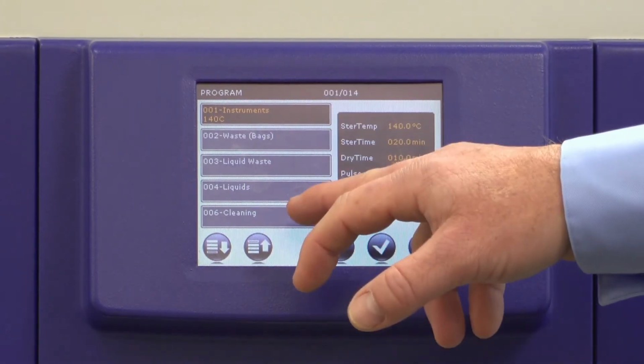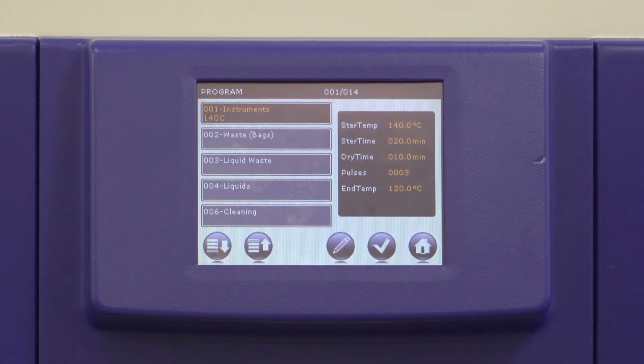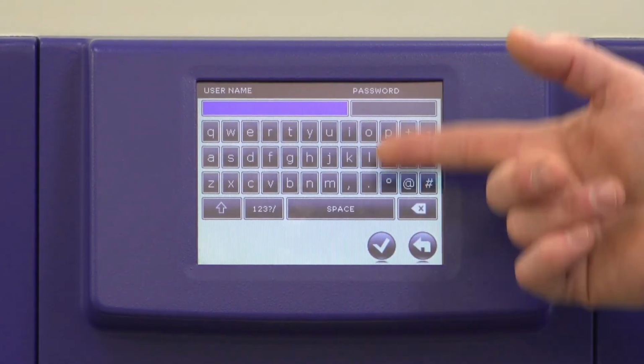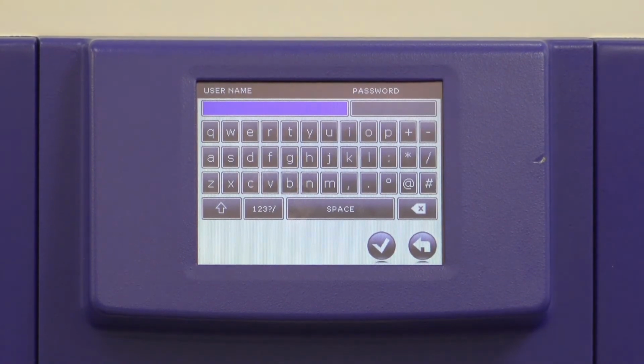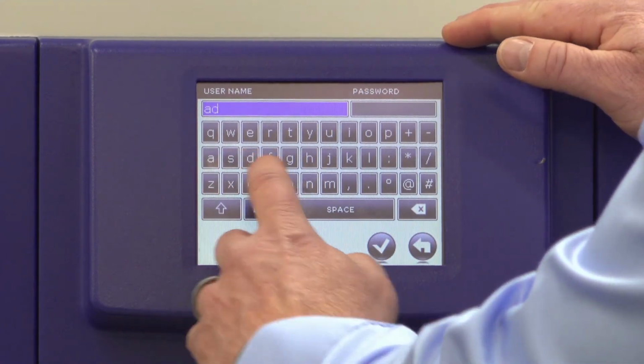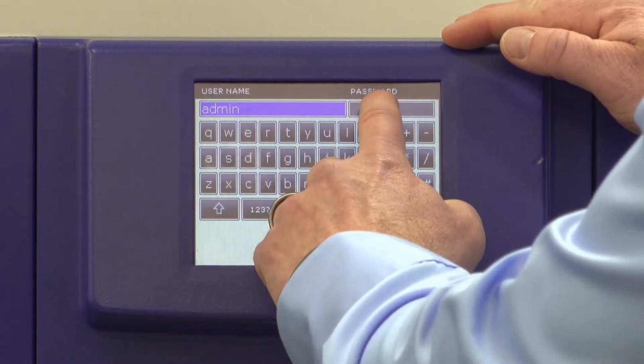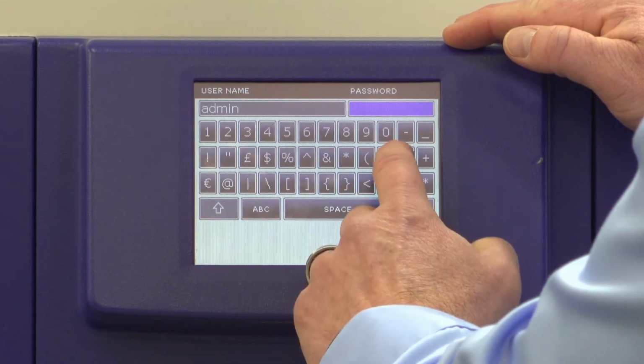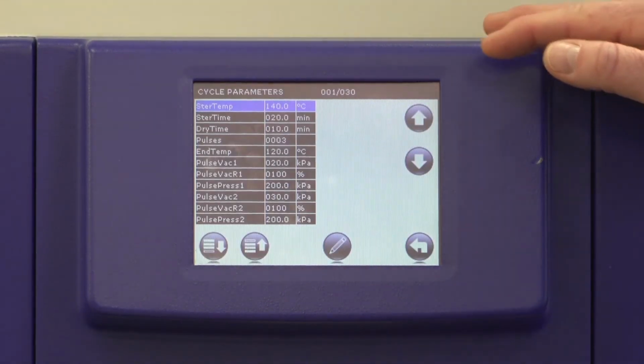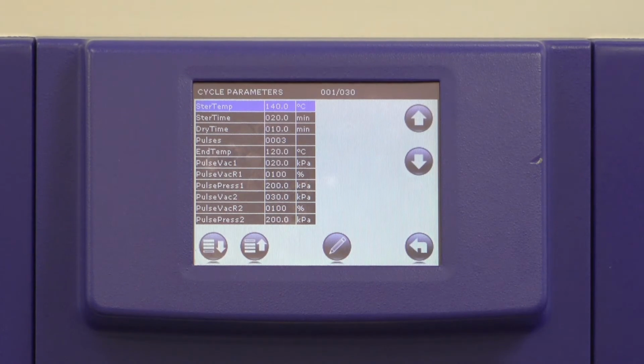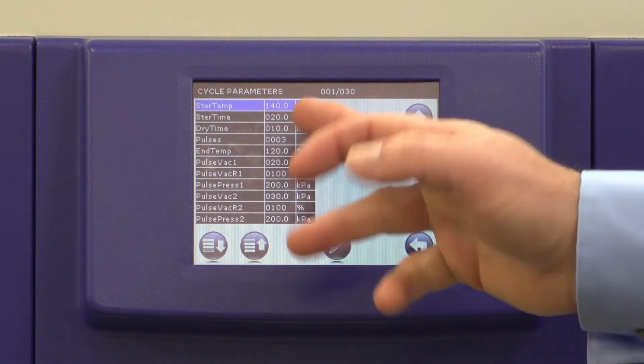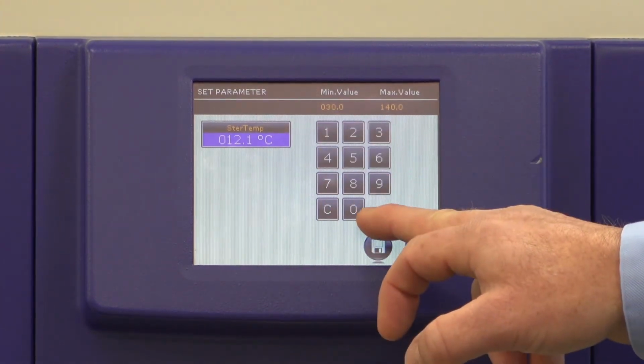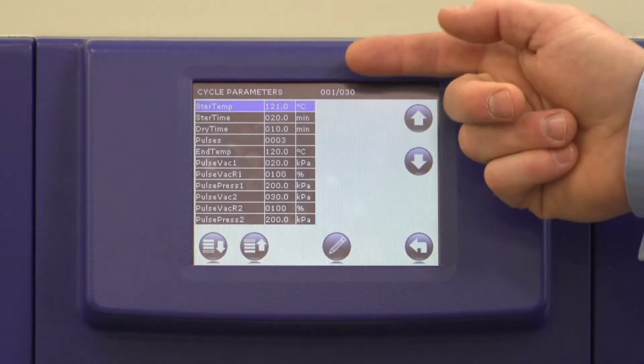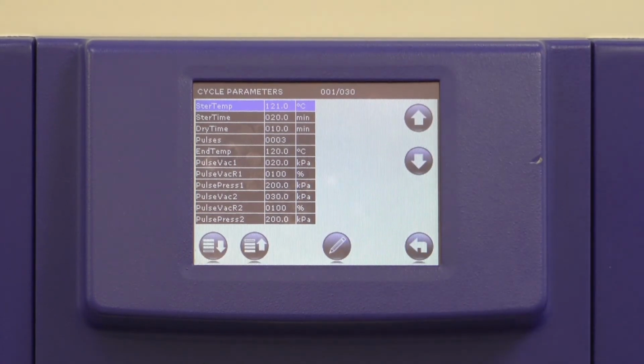All of them can be individually named. They're also password secure as well. So if I wanted to change something, it's going to ask me for a username and a password before I can prompt and go forward to access that information. Once I've entered that information, I can go to the different parameters inside of here. First would be sterilization temperature. If I just go to the pencil, I can tell it what temperature that I want that to be and just hit save. So I can save that for each individual parameter.